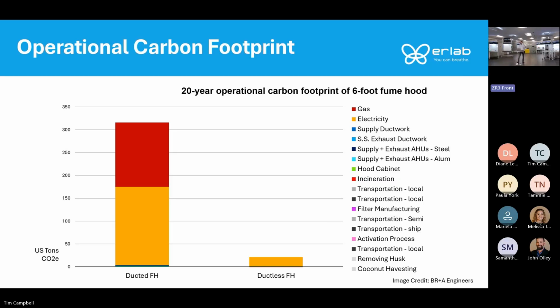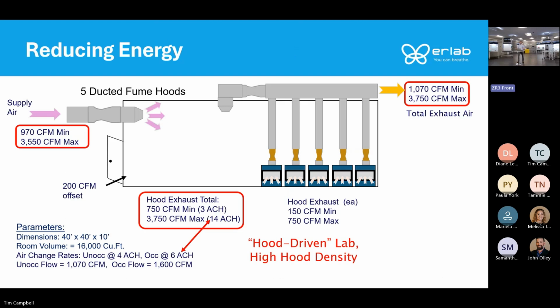If you look at the 20-year operational carbon footprint, there's a 94% reduction with the ductless fume hood. That all has to do with the makeup air, the gas and electricity needed to heat and cool the air that is being exhausted through the ducted fume hood. And where you see the most energy savings is in a high density fume hood lab. So if you work in a lab with multiple fume hoods, there's a chance that the space is overventilated. Most of the labs we deal with are typically about 6 air changes per hour when they're occupied. Depending on the size of your lab space and the number of ducted fume hoods in there, you may be well over that air change rate when all those hoods are in use.